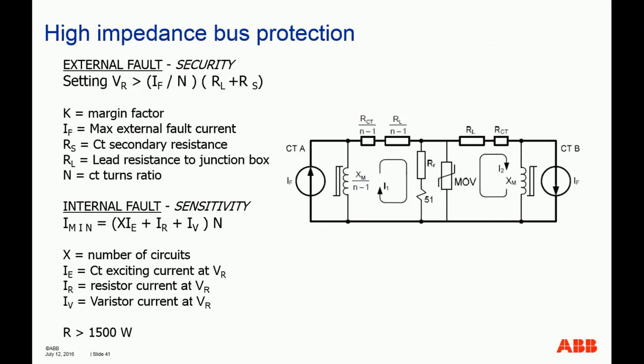The reason is that, here is actually a dissection of this type of high impedance relay wiring. As you can see, for a high impedance relay, you put a big resistor in series with your operating coil, and you put the MOV. The MOV is a device that will short after the voltage reaches a certain level. The reason is to protect the insulation of the cable of the wiring, because you don't want too high a voltage imposed on all those cable insulations for too long a time. So you want to have the MOV here.